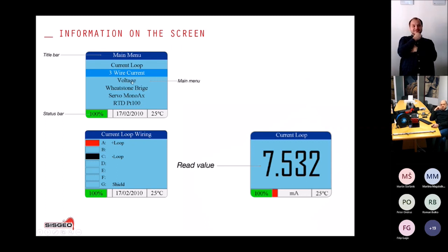You have the main information on the screen. For example, you can choose which output of the sensor you want to read. You have the percentage of charge of the internal battery, the actual date, and the internal temperature of the readout. The readout, like all Sisgeo readouts, guides the user on how to connect the sensor wires to the reading cable, and then the sensor reading clearly appears on the screen.